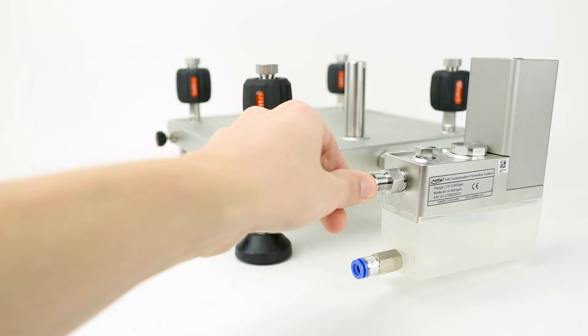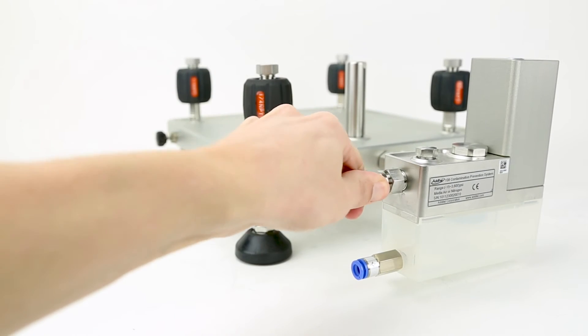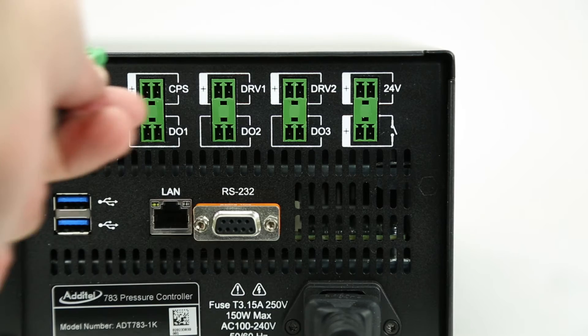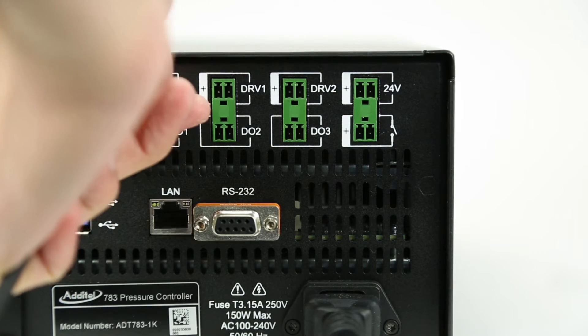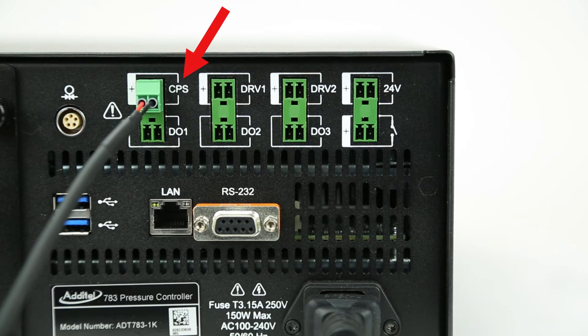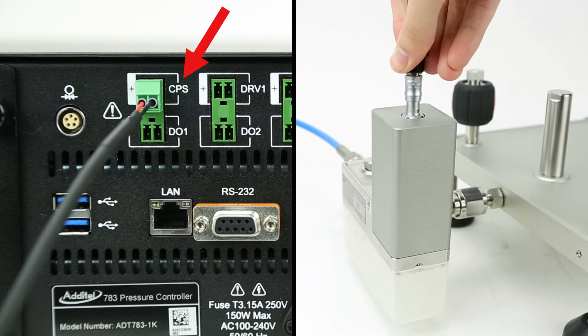Next, connect the pressure hose from the controller to the back of the CPS. Finally, connect the included communication cable from the CPS port on the back of the controller to the port on the top of the CPS itself.